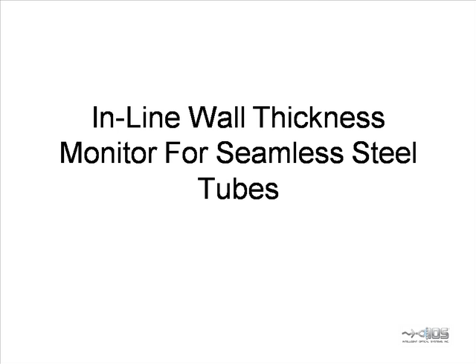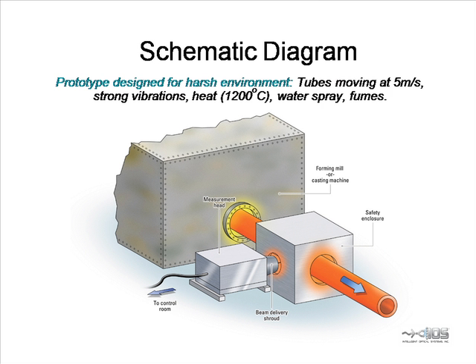The first application is an inline wall thickness monitor for seamless steel tubes. The requirement was to monitor the wall thickness of hot tubes as they exit a forming mill. A measurement head containing both lasers is placed alongside the tube as it exits the mill. Both laser beams are directed to the tube surface and a shroud surrounds the measurement position for the purpose of eye safety.